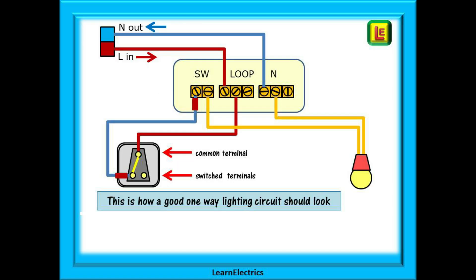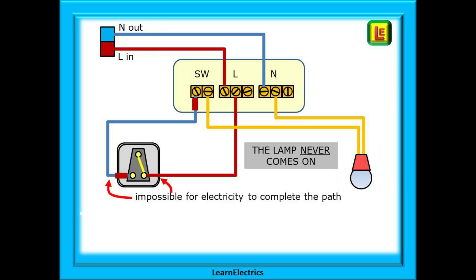Here is a good lighting circuit, fault free. Current can flow into the circuit through the loop, down to a switch terminal, through the switch to the common terminal, and up to the switch block. Current then travels along the lamp wire, through the lamp, and back to the neutral block. From the neutral block it then travels back to the consumer unit — if all this happens, the lamp will light up. Now look at this circuit: the two wires at the switch are connected one into each switch terminal but none in the common. Unless one of these is in the common terminal, nothing is ever going to happen. It is impossible for the electricity to complete the path back to the ceiling rose and the lamp will never light up.